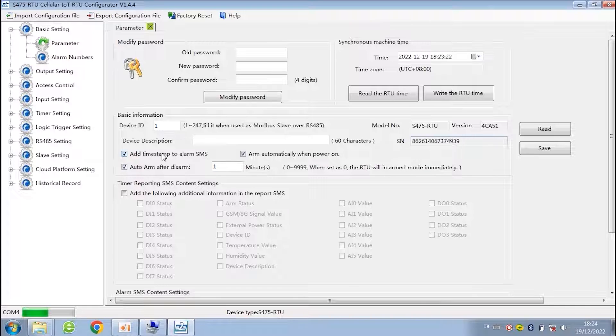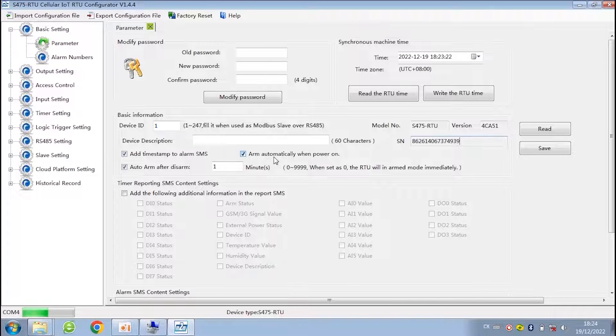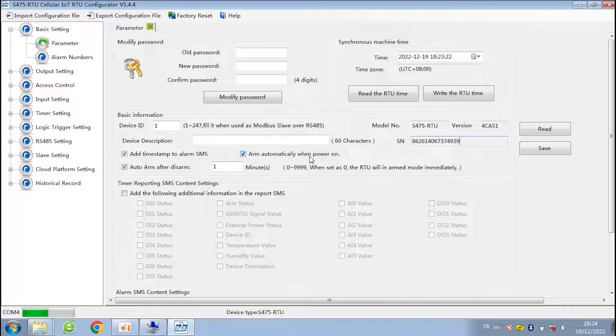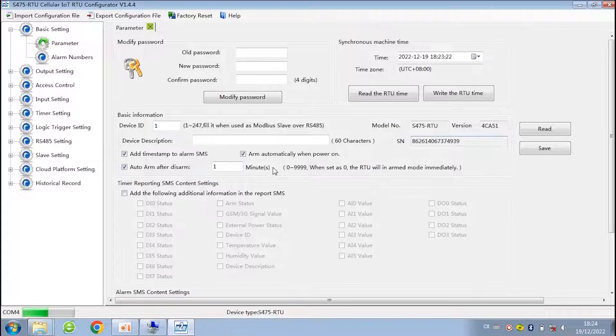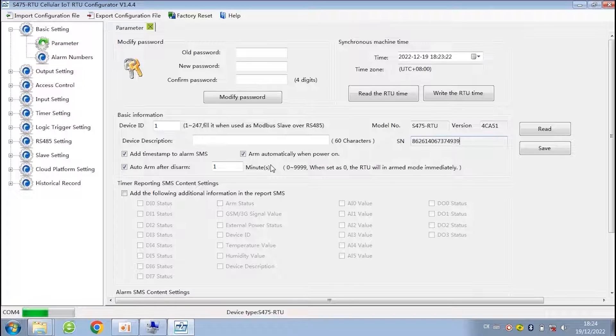Here are some options of SMS alarm, such as add timestamp to alarm, arm automatically when power on, and the period to automatically arm after disarm. The device will not trigger any alarm if it is in the disarm state. When it is in arm state, the state of DI changed, like normally open changed to normally closed, the alarm will be triggered.